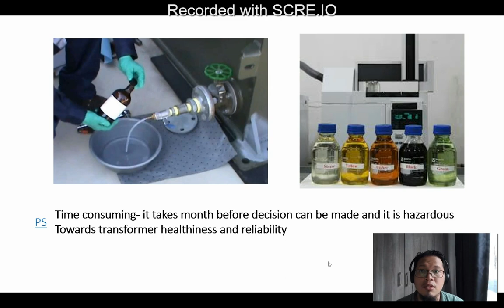This is time consuming, it takes months before a decision can be made. It is hazardous to transformer healthiness and reliability, because when PD happens, the severity itself may impact operations. Based on my experience working in TNB before, we had a transformer that caught fire due to PD, so these decisions are very important to preserve our transformer.